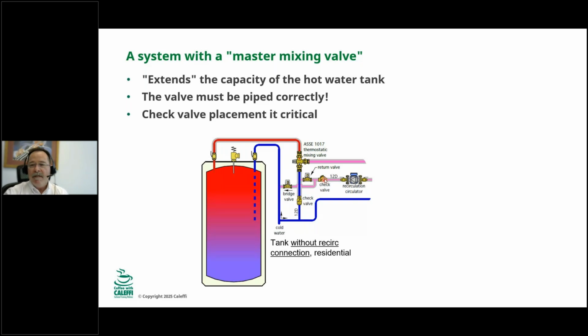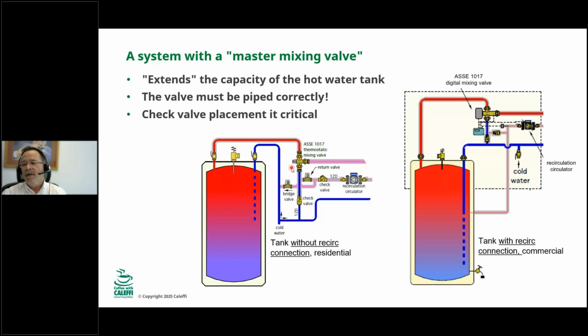If you have a tank that has a recirculation connection, I would say that's going to be a commercial tank, right? I don't know of any residential tanks that have a connection. But what you do is you come back, here's that same recirculation circulator, and the water either goes here, which is the same place, right? It's the cold inlet of the mixing valve, and then you tee off and then you go to your tank. So the piping is a little bit different, whether you have a tank with or without a recirc connection.